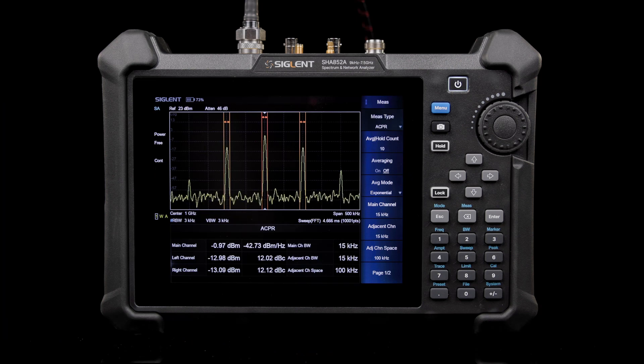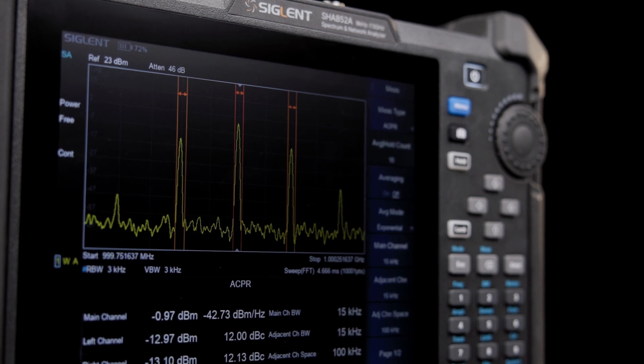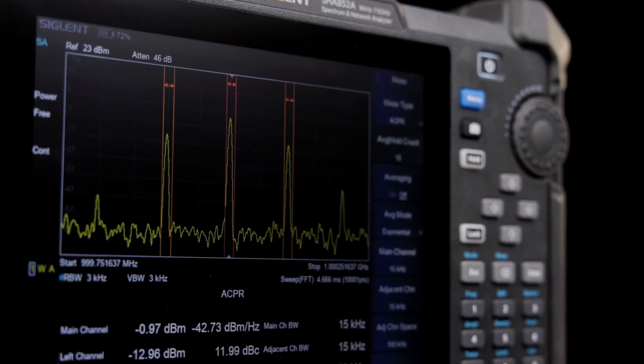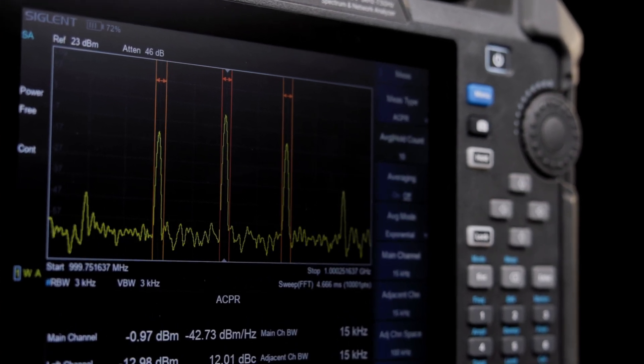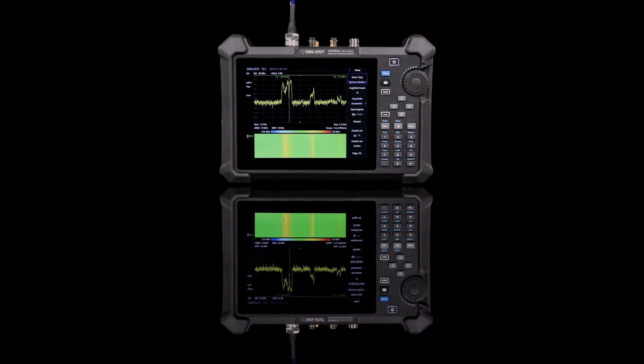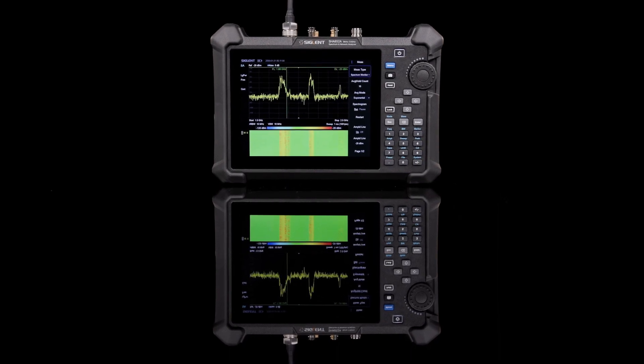Characterize signals and devices further with the SHA-850A's flexible measurement modes. Spectrum analysis mode offers an advanced measurement kit that includes standardized measurements like channel power, third order intercept, as well as a spectrogram or waterfall view.